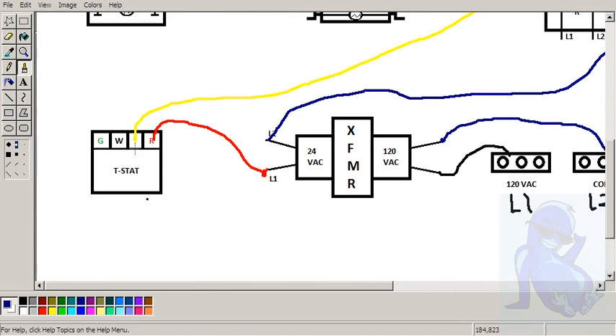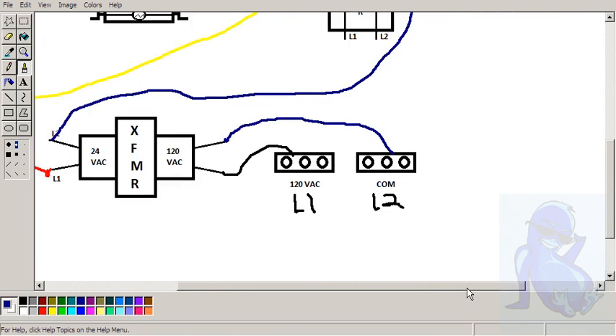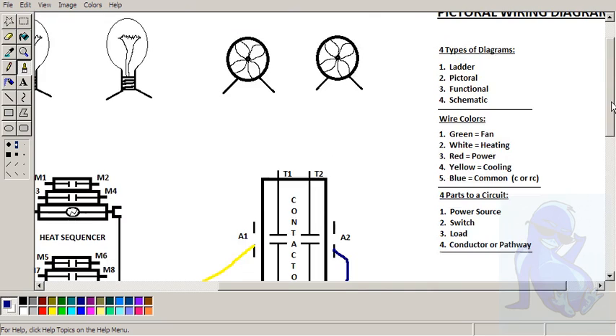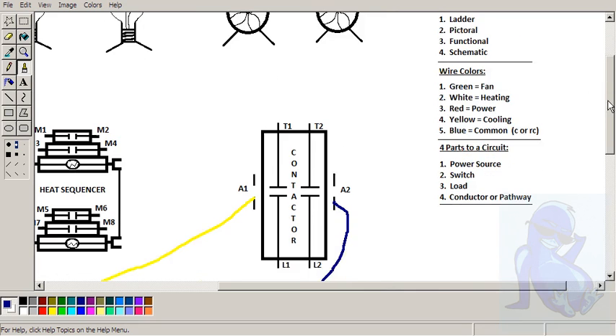L1 to switch, here's your switch, switch to load, load back to L2, and in this case it's a low voltage circuit, L1 and L2. This is L1 and L2 for your high voltage circuit. This is an example of a pictorial diagram. There's 4 types of diagrams. There's ladder diagrams, there's pictorial diagrams, there's functional diagrams, and there's schematic diagrams. Functional is more of those little boxes, and then schematics, usually what you see on the inside of a panel. When you take off a panel on an air conditioning unit, you're going to see the schematic. A lot of the symbols are going to be similar.